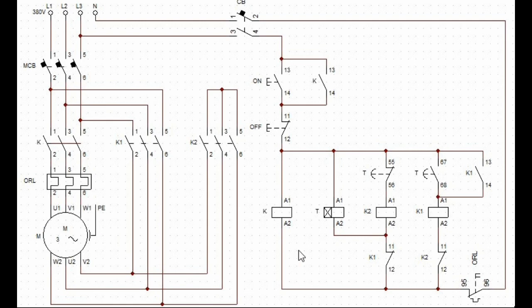Also from the on switch, a direct line is connected to normally open contact 13 of contactor K1, which will turn to closed contact upon K1 energizing and will supply power to the K1 coil when the timer cuts the line at contact 67 and 68.